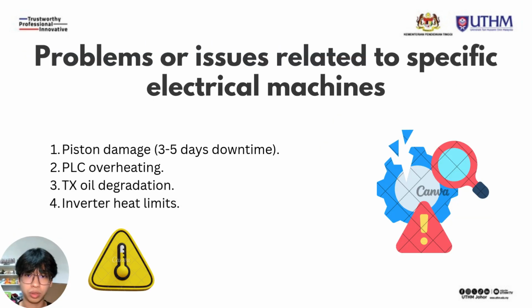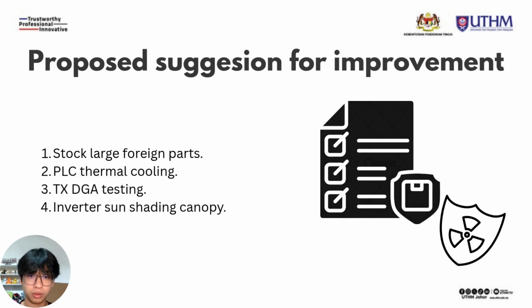Despite this robust system, we noticed some significant operational issues. First, generator pistons frequently suffer physical damage, causing costly downtime of 3 to 5 days. Second, the PLCs are prone to failing due to overheating in the harsh factory environment. Third, the continuous heavy loading on the transformers accelerates the degradation of the internal insulation oil. And lastly, the Solis PV inverter operates in a hot tropical climate, pushing it dangerously close to its 60 degrees Celsius maximum operating temperature.